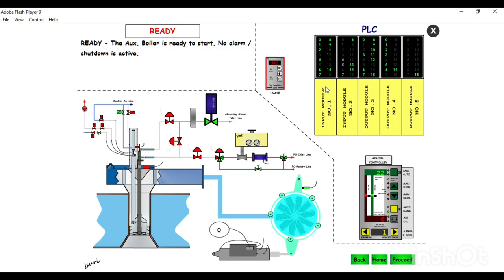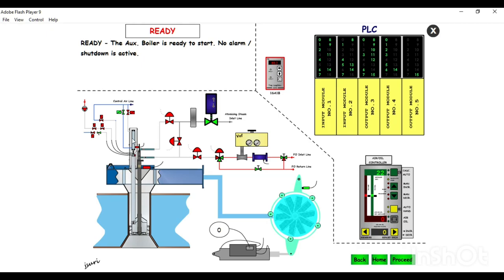In input module number one: point zero is for too low water level - the water level controller will give an alarm and the signal goes to the PLC input module. Point one is for high steam pressure, point two is for low atomizing steam, point four is for lance inserted - whether the burner lance is inserted or not. Point six is for high oil temperature, point seven is for low oil pressure.